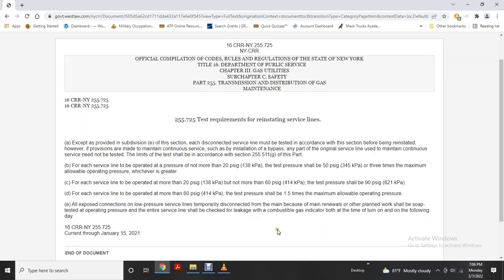the maximum allowable operating pressure. All exposed connections to low pressure services temporarily disconnected from the main because of main renewals or other planned work shall be soap tested. At operating pressure, the entire service line is checked for leakage with a combustible gas indicator, both at the time of turn on and on the following day.